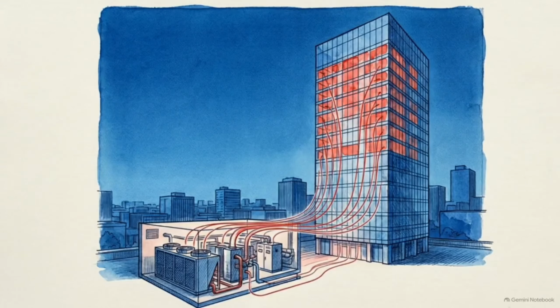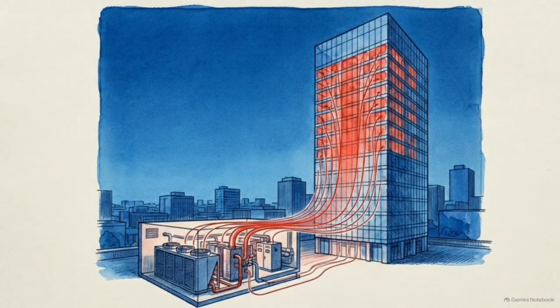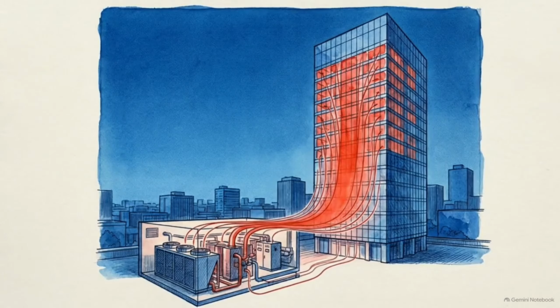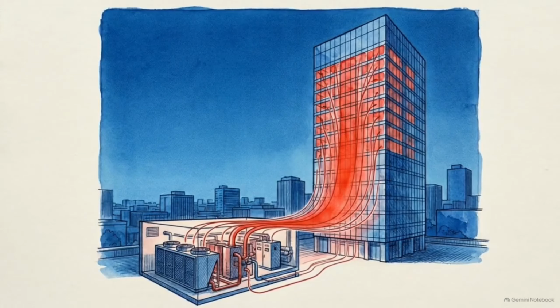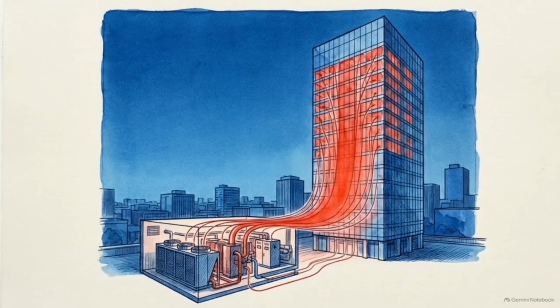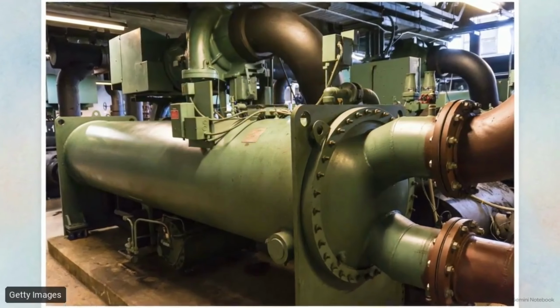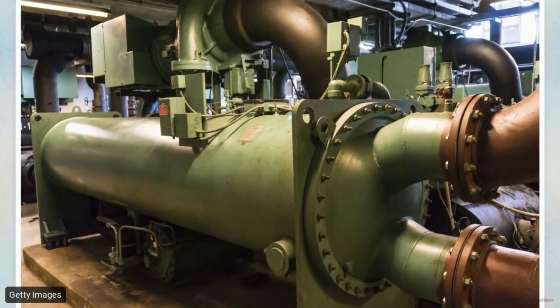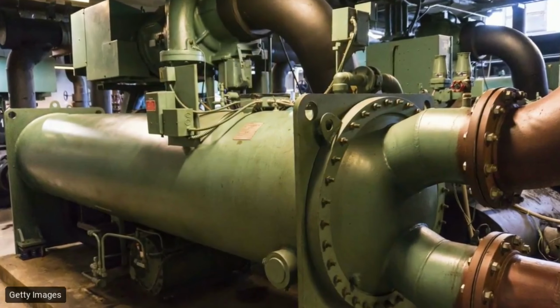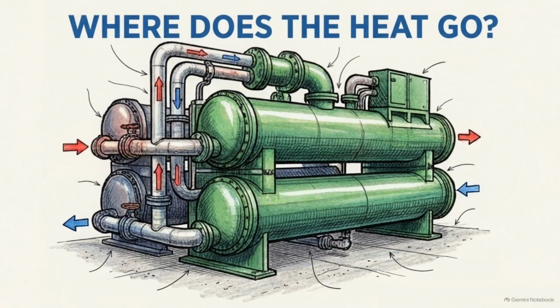A commercial water-cooled chiller removes hundreds of tons of heat from a building every hour. But thermodynamics dictates this thermal energy cannot simply vanish. Instead, the chiller absorbs this massive load, transferring it directly into a closed condenser water loop. This leaves a critical problem. To reset the refrigeration cycle, the chiller must find a place to dump this concentrated heat.